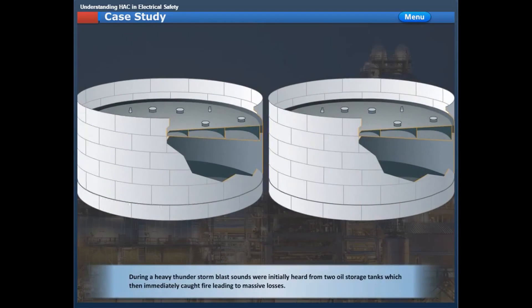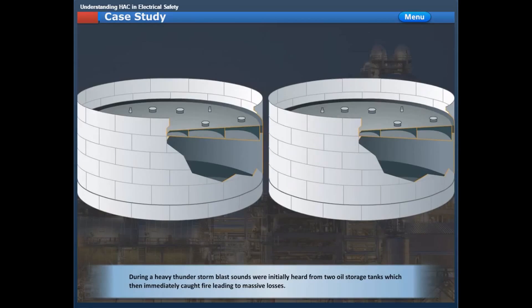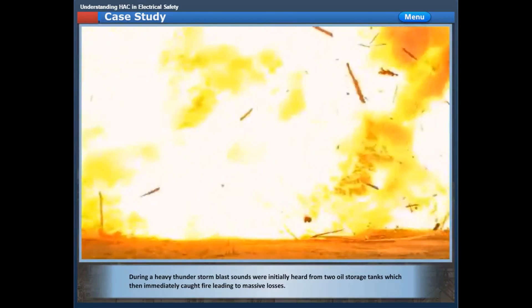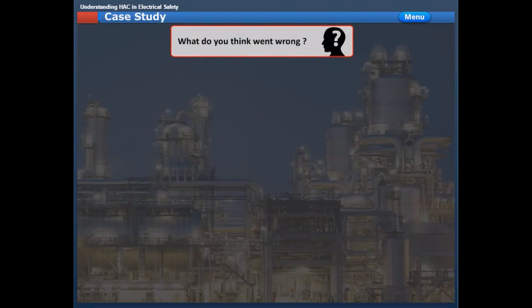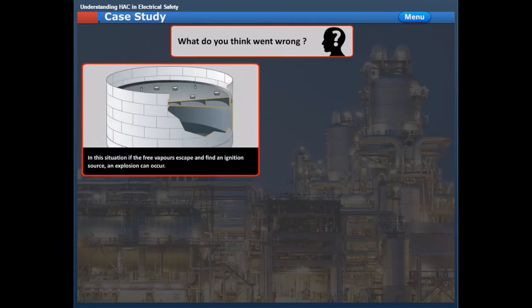During a heavy thunderstorm, blast sounds were initially heard from two oil storage tanks, which then immediately caught fire, leading to massive losses. What do you think went wrong? In this situation, if the free vapors escape and find an ignition source, an explosion can occur.